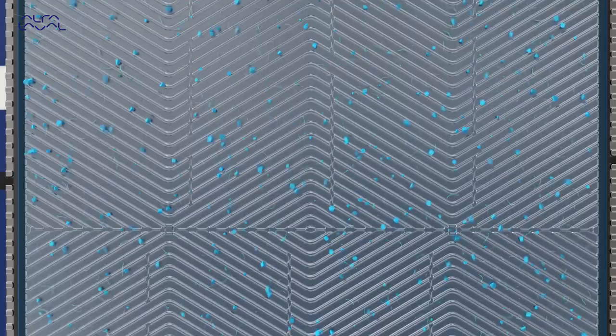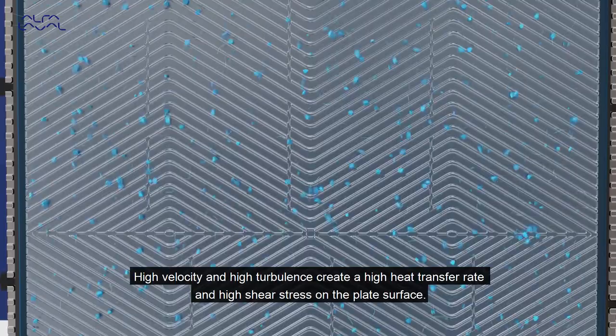As the fluid moves up the channels it is heated under pressure. High velocity and high turbulence create a high heat transfer rate and high shear stress on the plate surface. The high shear stress prevents solids from accumulating on the plate enabling a continuous self-cleaning effect.